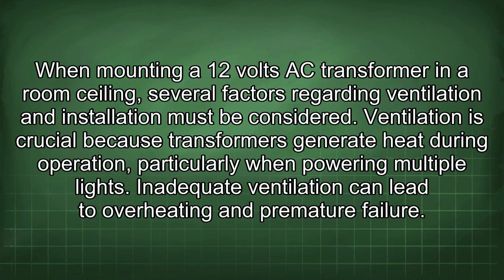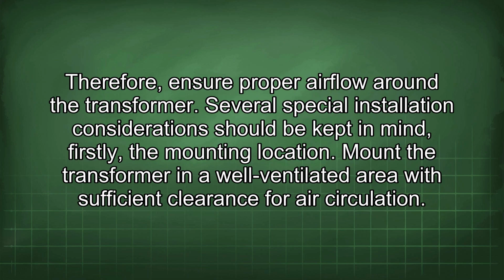When mounting a 12 volts AC transformer in a room ceiling, several factors regarding ventilation and installation must be considered. Ventilation is crucial because transformers generate heat during operation, particularly when powering multiple lights. Inadequate ventilation can lead to overheating and premature failure. Therefore, ensure proper airflow around the transformer.